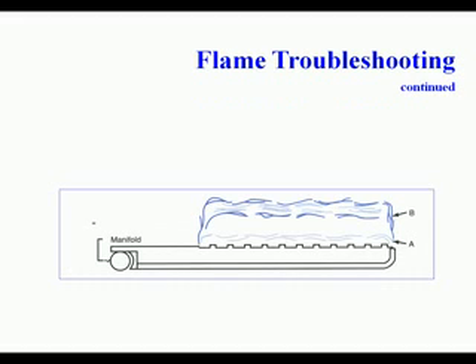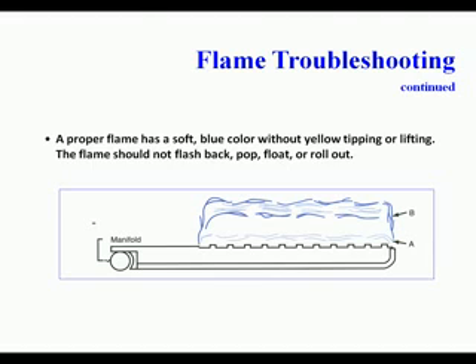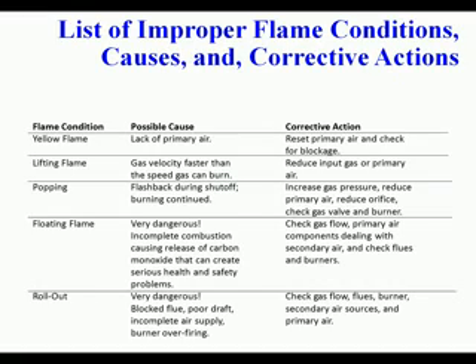To troubleshoot furnaces, you can use the flame. Proper startup and operation of a furnace requires the correct fuel-air mixtures, gas pressures, and flames. Primary air promotes complete combustion. The amount of primary air entering the burner is controlled by adjusting a shutter. If no shutter is present, refer to the manufacturer's literature on how to adjust the primary air. The proper flame has a soft blue color without yellow tipping or lifting. The flame should not flash back, pop, float, or roll out.